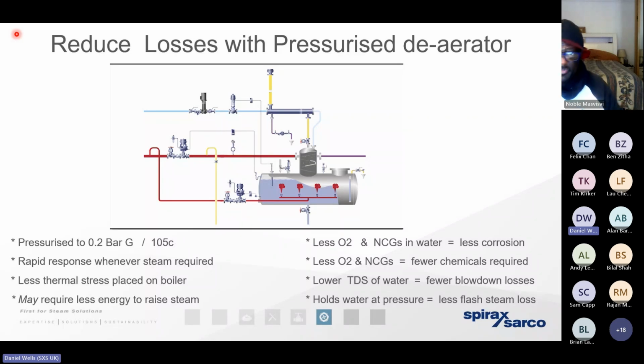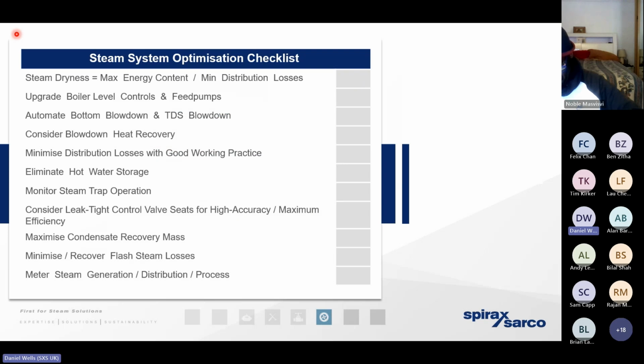And another benefit is by pressurizing the water, we've purged off a lot of the oxygen and the non-condensable gases, which you'll remember from previous presentations require a significant amount of chemical treatment, which is another reason why we then need to blow down that high concentration of chemicals. That's simply not required if we can pressurize the water. But better still, it means we've now got an excellent heat sink that we can direct those flash steam emissions to. So it means that we're moving closer and closer towards a zero net loss steam system. So quick checklist for you up on the screen.